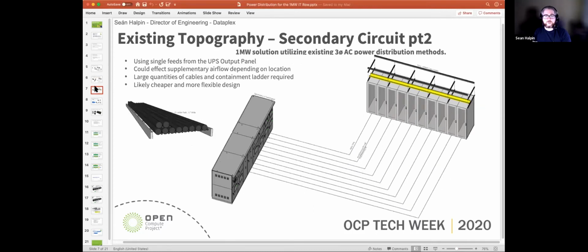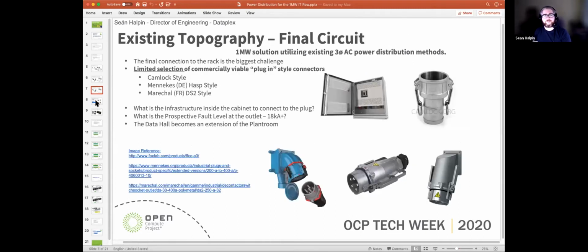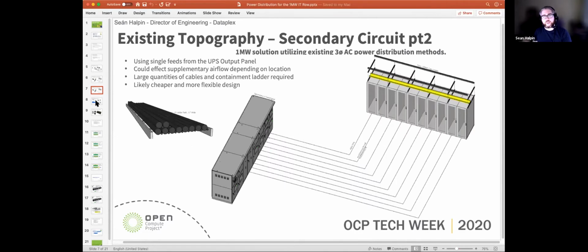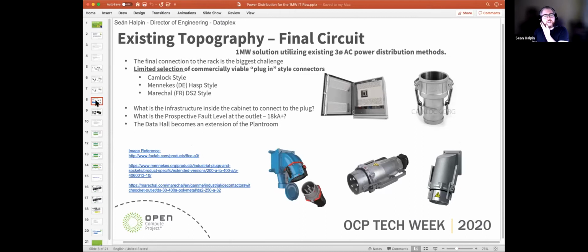The second option is the standard whip, where you'd be feeding 160 to 250 amp MCCBs out onto your rack with a standard Hofer cable or something similar. But realistically, the biggest challenge is the interface between the infrastructure and the rack, which is where Gabi is going now. That's kind of where we're limited at the moment.